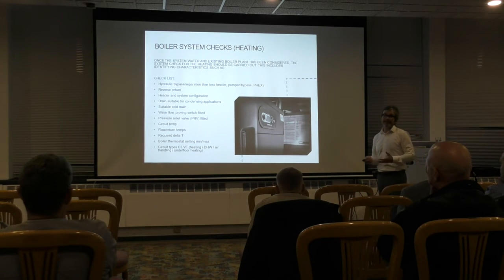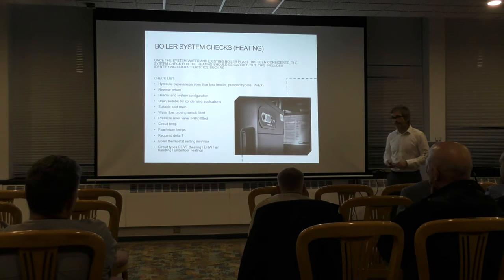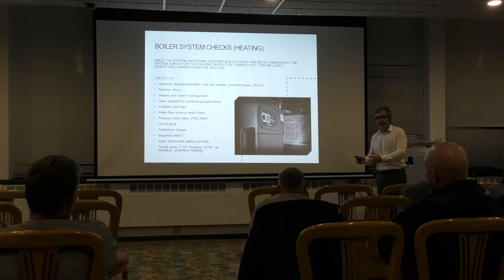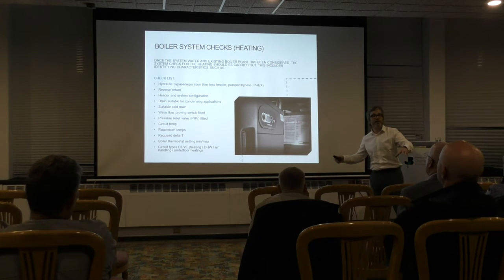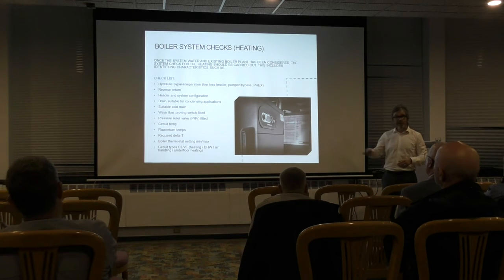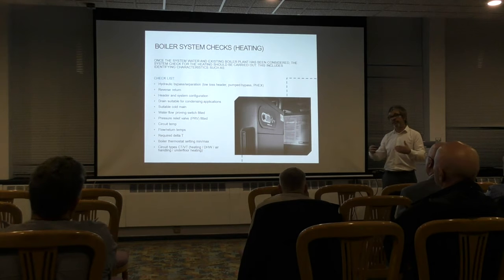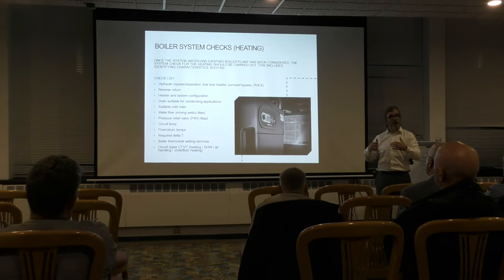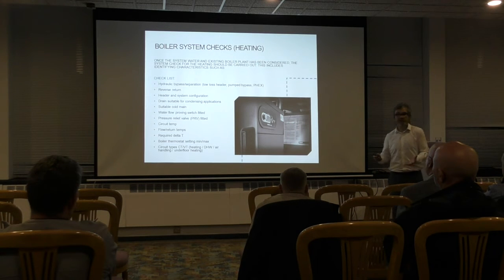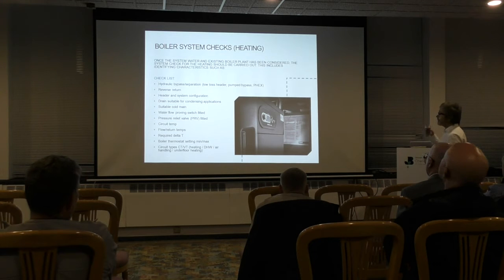Reverse return. Again, if you've got a bank of boilers, and we're looking at maybe one shunt pump, or maybe a twin head shunt pump going over maybe three or four boilers, if you do it reverse return, then you'll get the correct flow across each of the boilers. So if we're looking at a bank of boilers and we're putting a shunt pump on the back of each boiler, then you wouldn't have to go reverse return, because you're going to get the correct flow rate across each of those appliances. The header and system configuration we've kind of already covered.